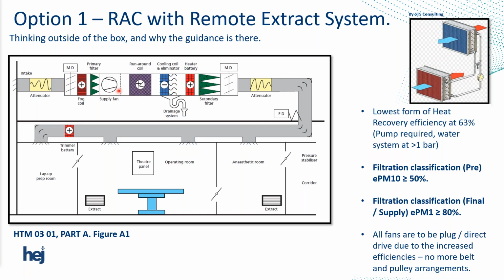The cooling coil sits on the discharge side of the fan. Now, there's an important reason for that. We can't have that on the suction side of the fan. We need it on the discharge side of the fan. The eliminator is shown on the drawing for velocities internal of the AHU greater than 2 meters a second. The reason that it's on the positive side of the fan is because the air hits dew point. We need it to be pushed away and drained into the system. We can't have pooling water this side of the coil or under the coil. It's got to be removed.